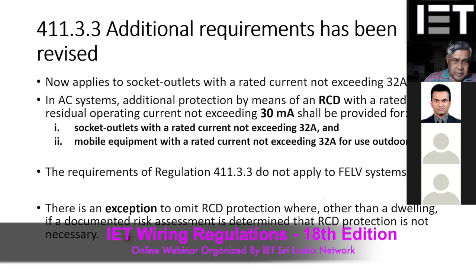Then there are certain additional requirements for the socket outlets as well. If you are supplying any socket outlet where the rated current is less than 32 ampere, then it's compulsory to wire them using a 30 milliampere RCD. Either a socket outlet, or even a mobile equipment where the rated current is less than 32 ampere, you have to protect them using a 30 milliampere RCD. So these are the new additions to the regulation, to give additional protection.